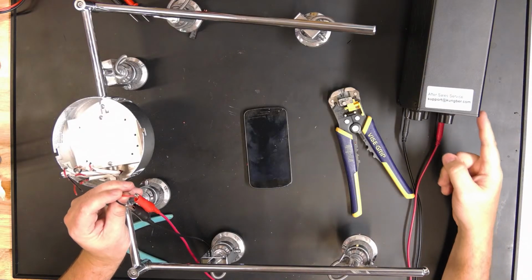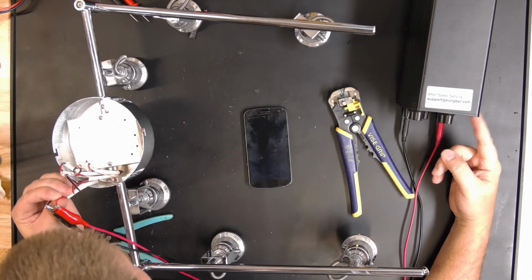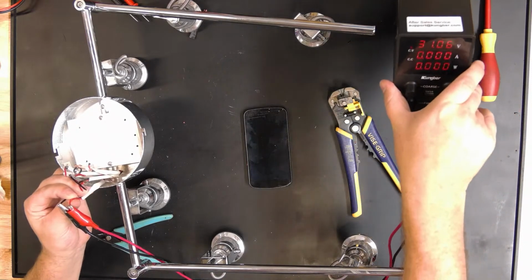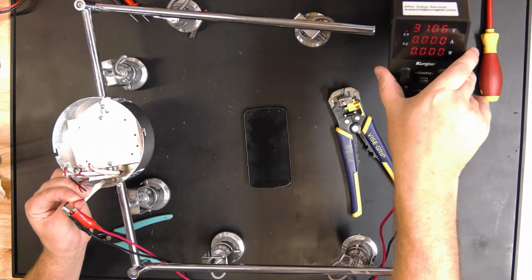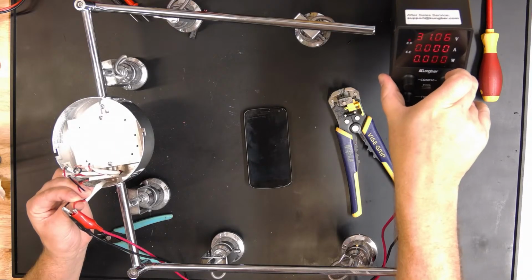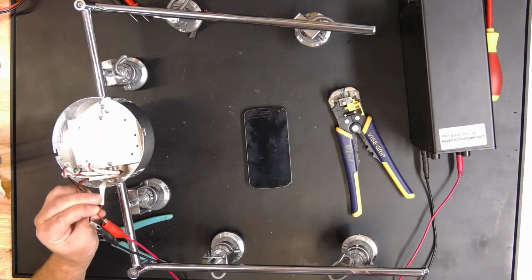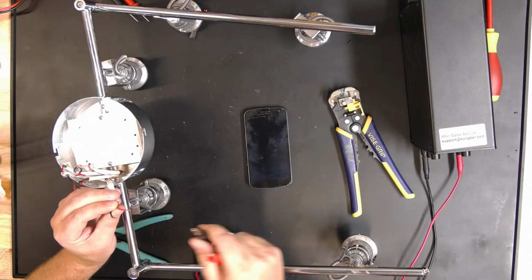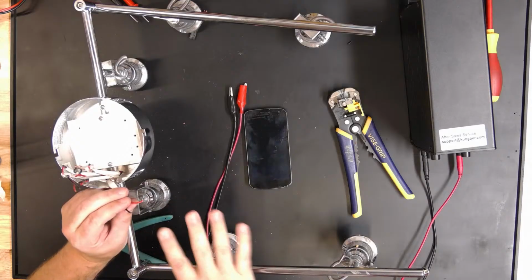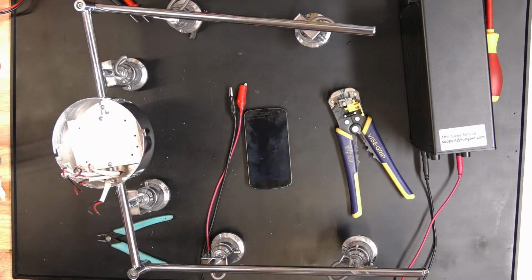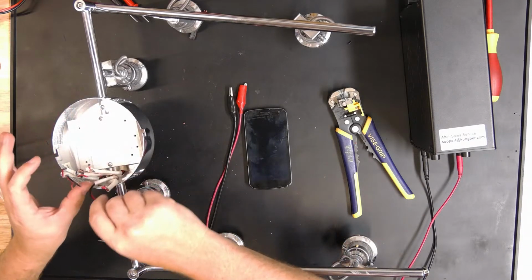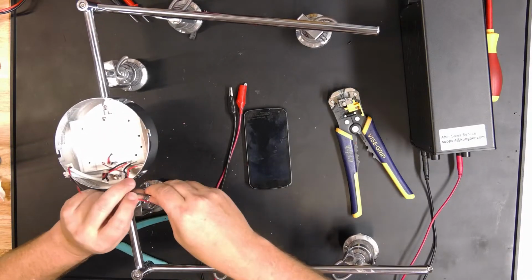I'm not showing anything over here either, by the way. So one of the things I do when I'm troubleshooting is you look over here on amps and watts, and it will tell you how much current is being pulled. And you can see I have no current being pulled by these. And I would assume that the polarity is correct. I assume that I'm doing everything correct. Hopefully they didn't do reverse polarity. We'll test it just to be sure, but that wouldn't make any sense.